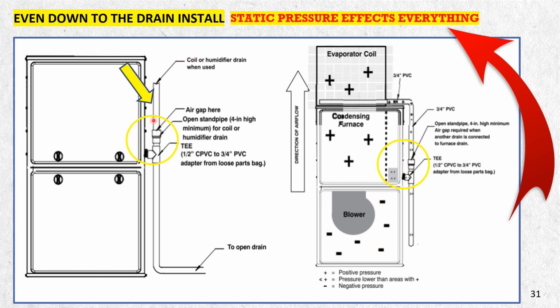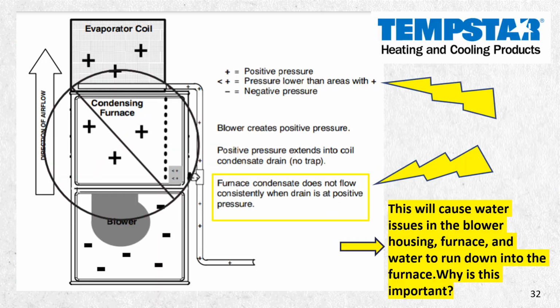Like here, if this went up, you'd have an air gap here. You could do it that way as well. These two ways are acceptable. This is not acceptable, where it's hard piped straight in, 90 down, hard pipe into a condensing furnace, and then run out. It will not drain. So here you can put a T, like a clean out, just don't put the cap on it. That would work.